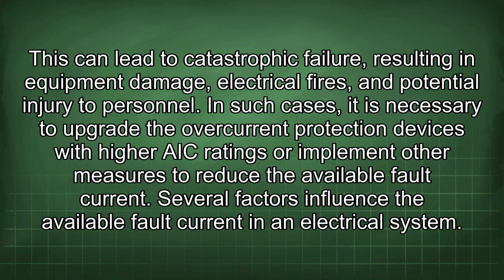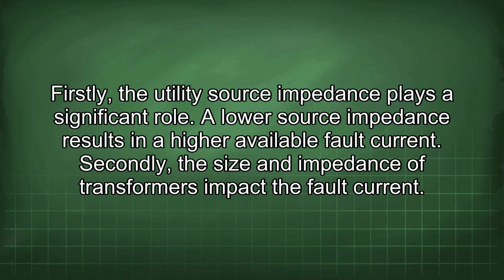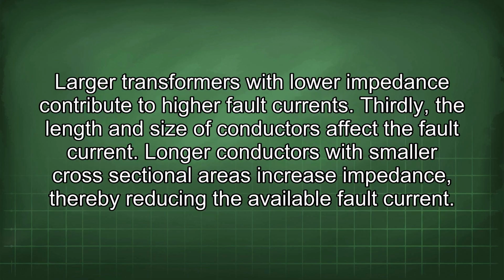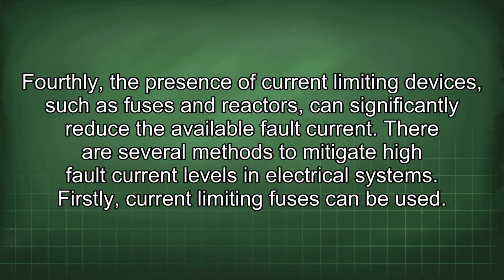Several factors influence the available fault current in an electrical system. Firstly, the utility source impedance plays a significant role. A lower source impedance results in a higher available fault current. Secondly, the size and impedance of transformers impact the fault current. Larger transformers with lower impedance contribute to higher fault currents. Thirdly, the length and size of conductors affect the fault current. Longer conductors with smaller cross-sectional areas increase impedance, thereby reducing the available fault current. Fourthly, the presence of current-limiting devices, such as fuses and reactors, can significantly reduce the available fault current.